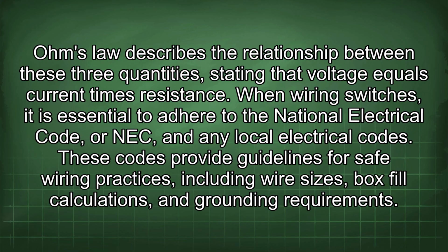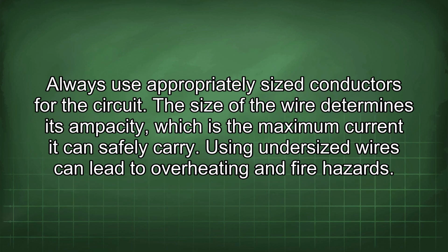When wiring switches, it is essential to adhere to the National Electrical Code, or NEC, and any local electrical codes. These codes provide guidelines for safe wiring practices, including wire sizes, box fill calculations, and grounding requirements. Always use appropriately sized conductors for the circuit. The size of the wire determines its ampacity, which is the maximum current it can safely carry. Using undersized wires can lead to overheating and fire hazards.